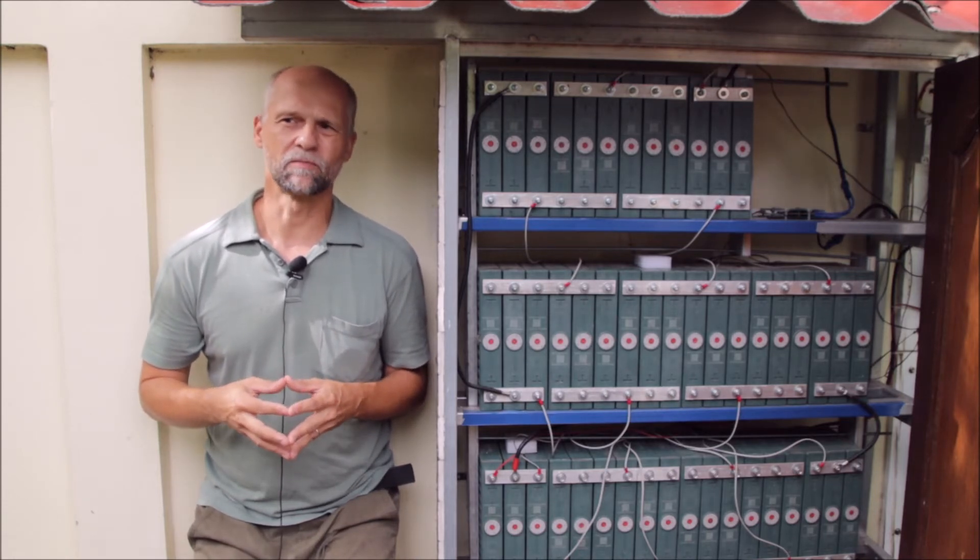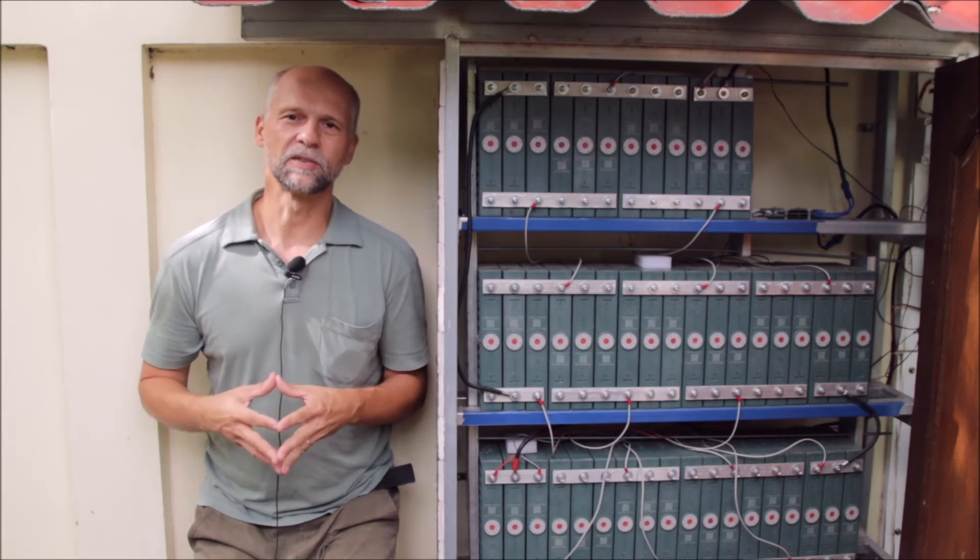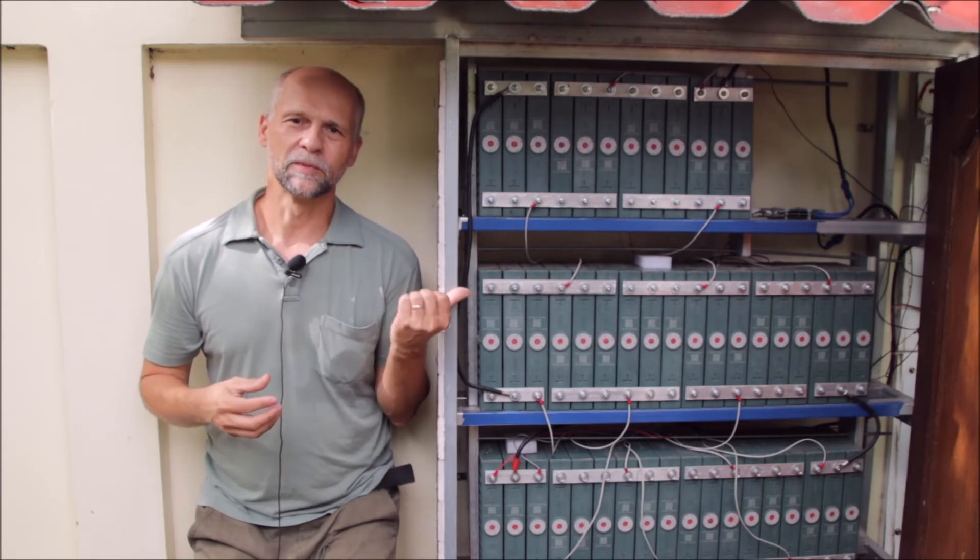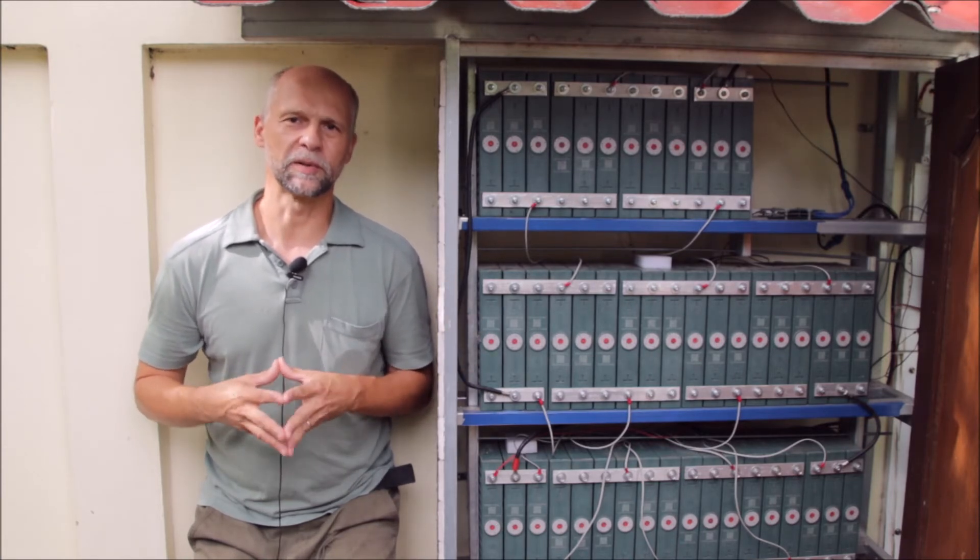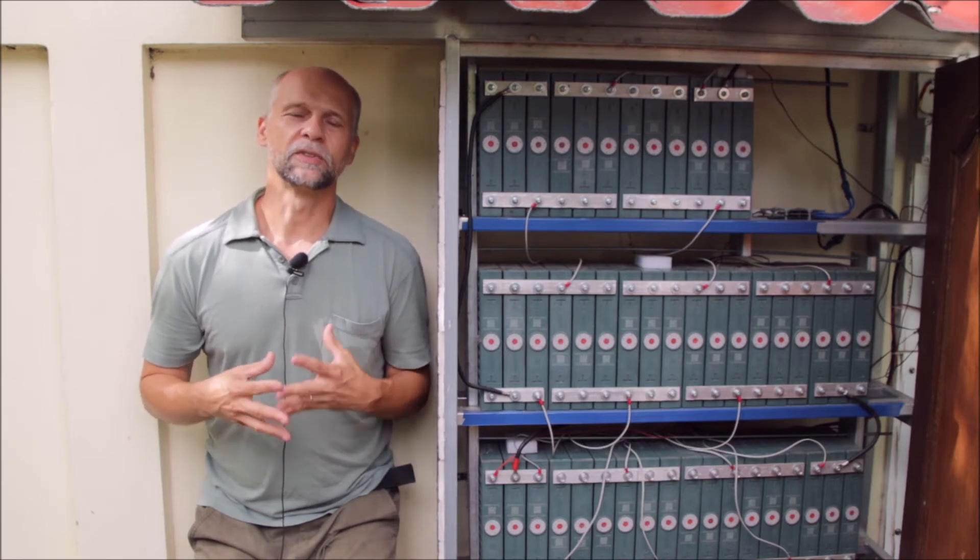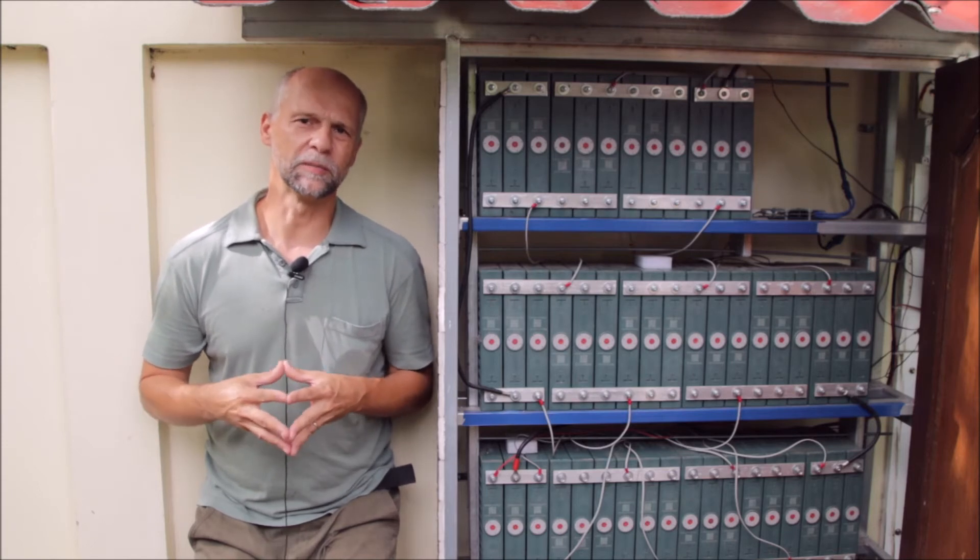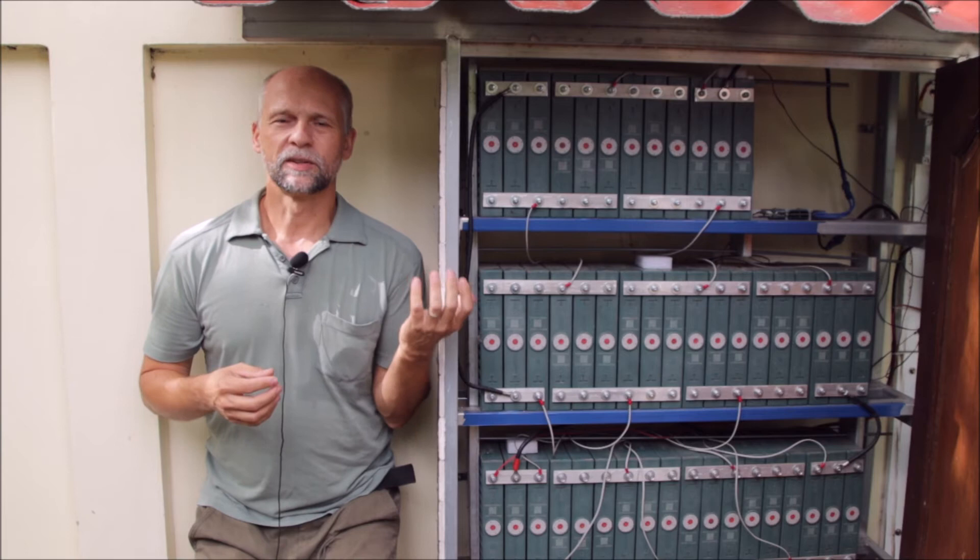Lithium iron phosphate, if you abuse this sort of cells, they will typically show abuse in a degradation of the cell capacity. If you over-discharge this pack, let's say you make a mistake and get this down to one and a half volts per cell, when you charge it up next time you might have lost 20% of capacity.